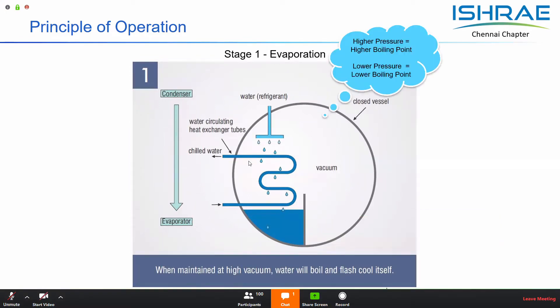When the refrigerant vapor is produced, there is a slight increase in pressure inside the chamber. To maintain a constant chilled water outlet temperature, we need to ensure that the vacuum levels are kept constant. This is done by the next heat exchanger, which is called the absorber.